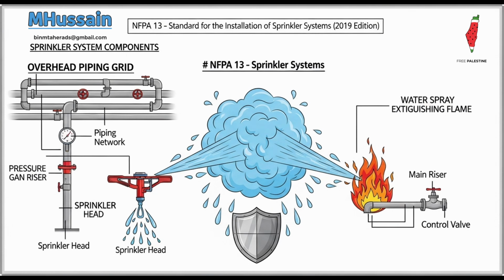Good question. CMSA sprinklers are designed primarily for control. They focus on limiting the size of the fire and preventing damage to the ceiling structure, basically holding the fire in check until the fire department can arrive for final extinguishment. ESFR sprinklers, on the other hand, are designed for suppression. They create large, high-momentum water droplets specifically designed to penetrate deep into the fire plume and actually impact the burning surface directly, thus achieving true extinguishment, ideally before significant fire growth.